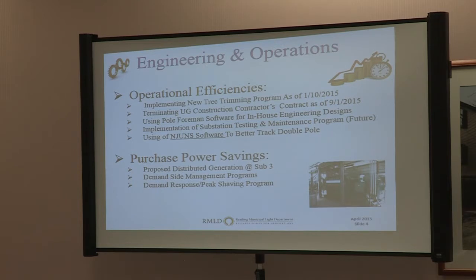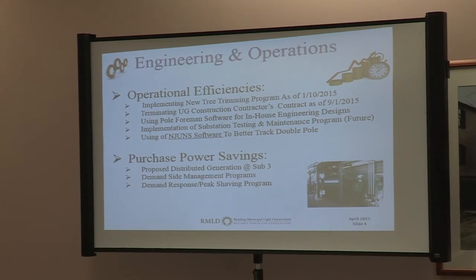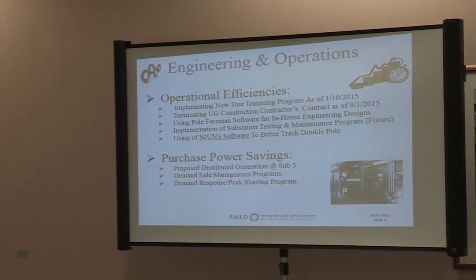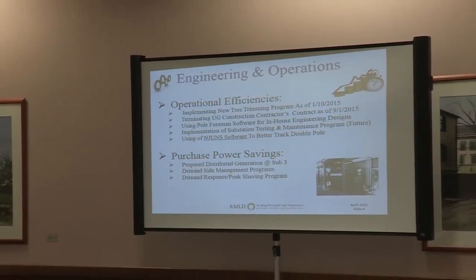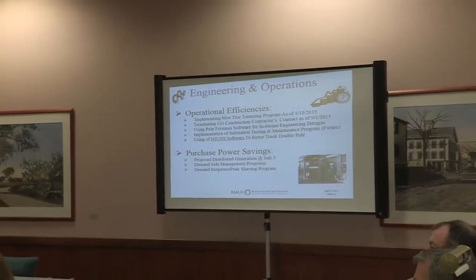The breaker that needed to be replaced, and also the 8 bushings of the transformers at station 4, the 115 kV / 35 kV substation transformers—the bushings tested bad and were on the verge of failure. We caught them before they failed, ordered them, and replaced them. The breaker is replaced, and some minor stuff is still left to do that we're getting to.